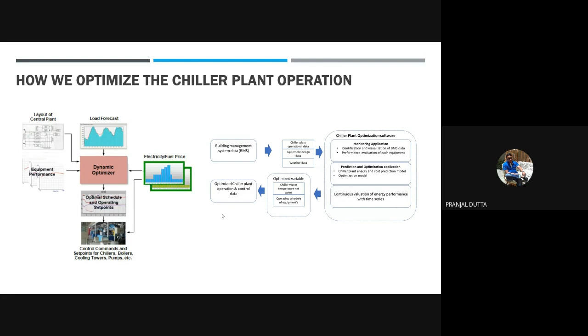This is the BMS system. Then chiller operation data needs to be input, equipment design data, then weather data, then monitoring application, then prediction optimization. Then it continues evaluating energy performance with the time series, optimizes the chilled water temperature set point and operating schedule, and finally it will optimize chiller plant operation and controls. So you don't need any controller on the chiller plant. Somebody just has to look into the data. If something is wrong, then he can take some intervention. Otherwise, it will operate automatically. So these are the processes.